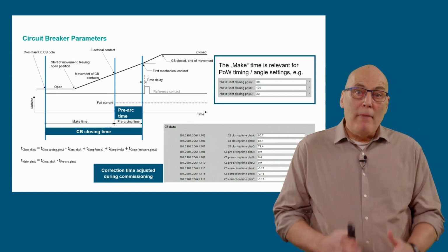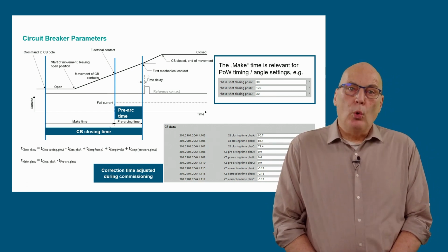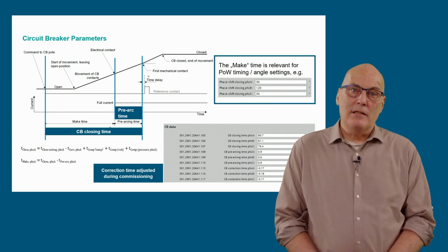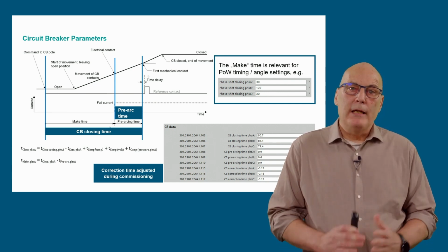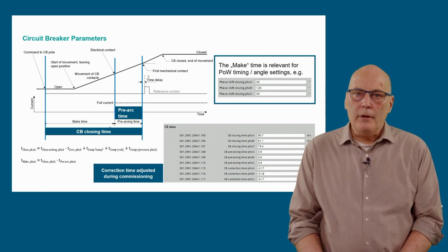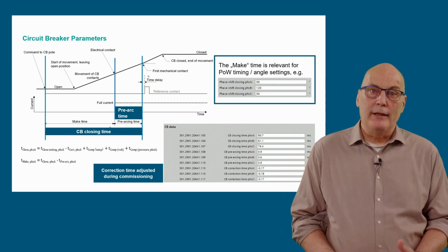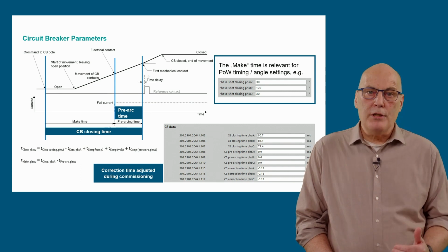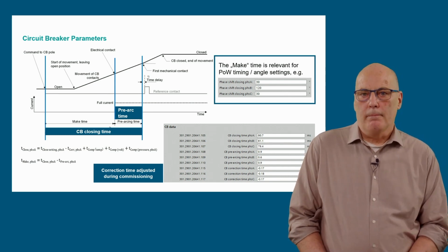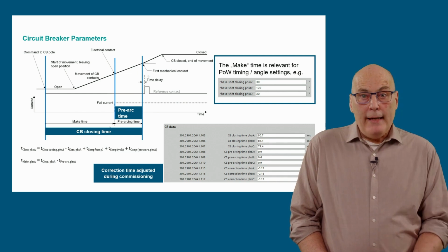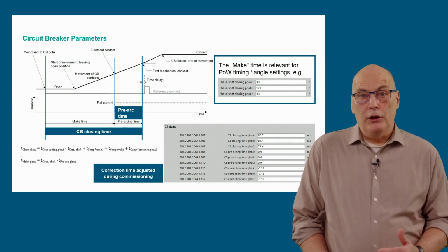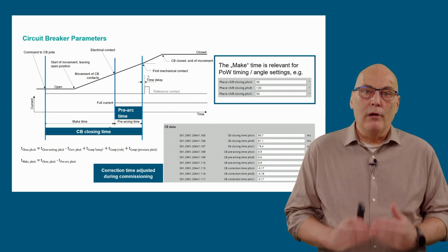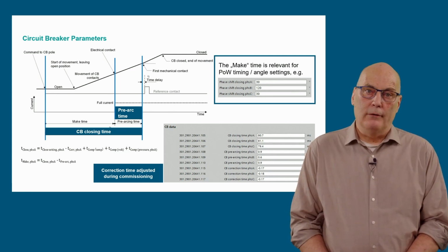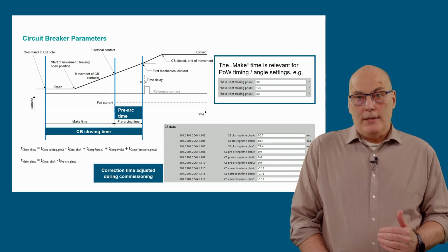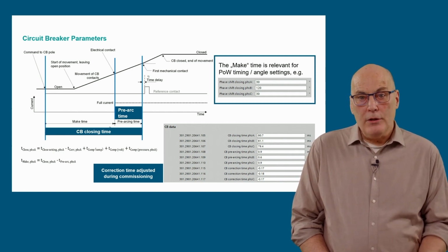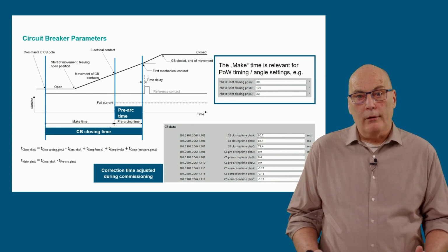Now, the make time. The make time is shorter than the closing time because it ends when current starts to flow, equals electrical contact. The definition of make time is simple, as shown in the second equation. It is the closing time minus the pre-arc time. The make time is used by the point-on-wave function to determine the instant of closing as set with the reference voltage angles. So, when analyzing, it is important to remember closing time is the starting point of all calculations.